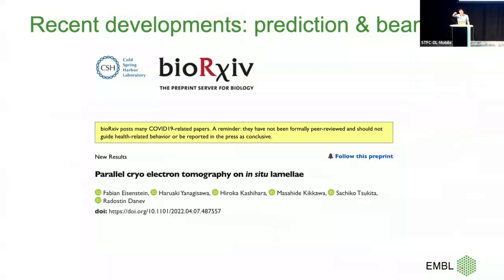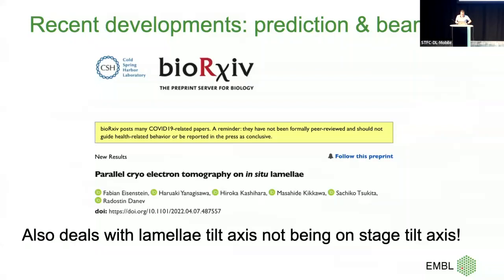You'd like the FIB lamella angle to match the stage tilt angle, but when you load the cartridges there's a bit of rotation so the lamella ends up tilted. That causes problems when you tilt the stage. You can solve it geometrically if you know the offset between the FIB tilt axis and the stage tilt axis — which is exactly what this method does. Sometimes, even when people try really hard to load lamella samples with the right orientation, you look in the microscope and they're completely rotated.